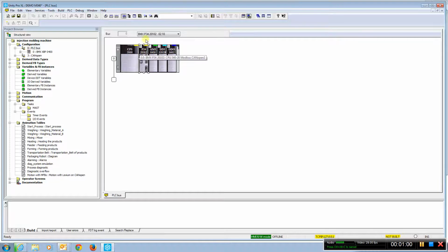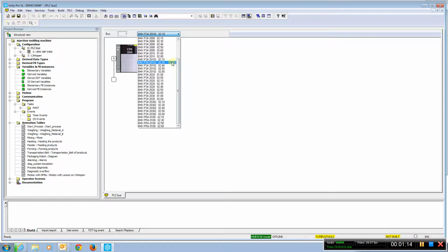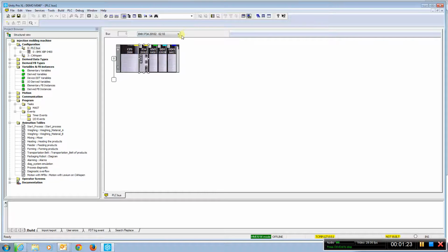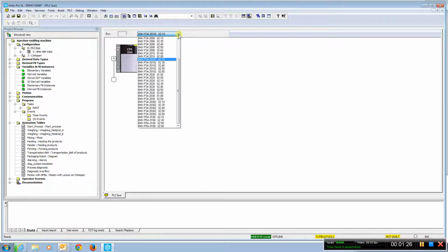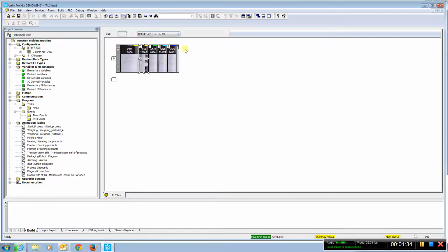The other thing that we need to look at is in the drop-down menu, we can see this is my PLC choice along with the firmware. Many times when you start a project from scratch, the firmware will be different in the PLC. So we either want to update that PLC choice. In this case, for that processor, I have firmwares all the way from 2.1 all the way up to 2.6. When I download, they need to match. Typically, if it's a new project, we're going to want to use the firmware updater and update it to the latest software and choose that for our PLC of choice. If you're going into an older processor and we don't need to mess with it, sometimes you have to go and downgrade this to make it match what's actually in the PLC.